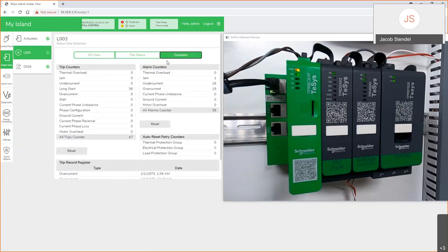Counters here can show you all the different alarms and how often they happen, and you can look at all the available forms of trips and alarms. You get your phase imbalance, current reversal, stall, all these different options that you can disable and enable. Decide from there what you want to do with your process. There are a lot of options on how you want to configure your setup. It's completely configurable to how you see it. So whether it be fans, pumps, conveyors, they have you covered there.